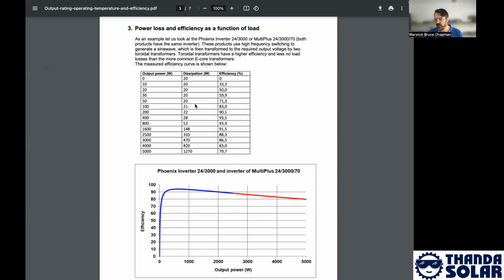So if we take that 800 divided by that 2400 watts, what we're saying is that the sweet spot for this particular inverter is around about 33% of its rated maximum wattage, power output. So at 33%, this particular inverter is most efficient. Now, at 3 kVA, sorry, at 2.5 kilowatts, which is around about 3 kVA, it's already losing 11.7% by converting DC to AC, by inverting DC to AC.